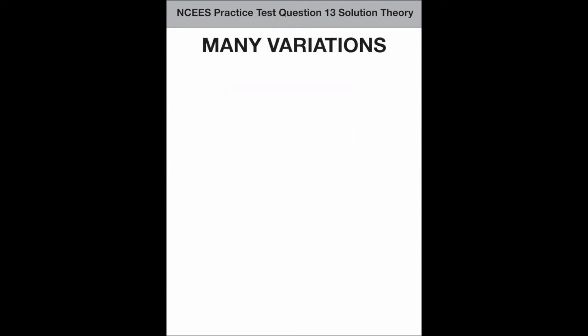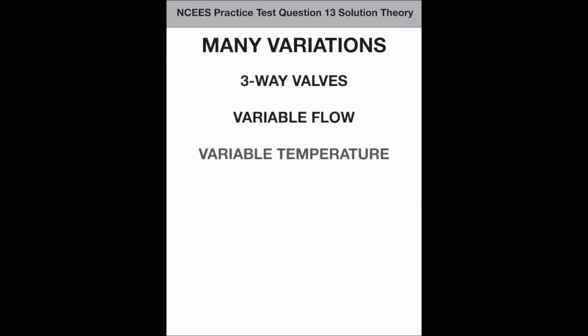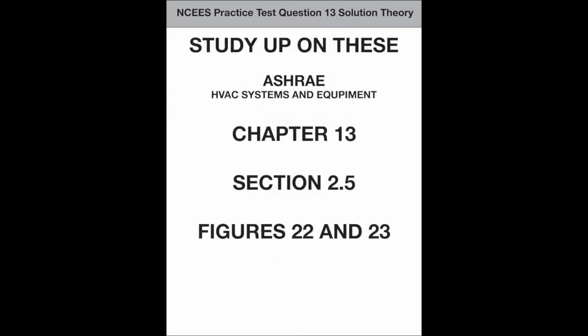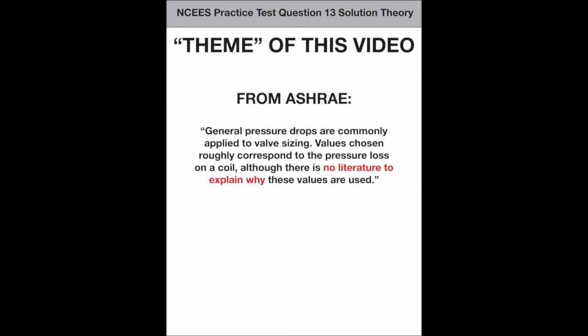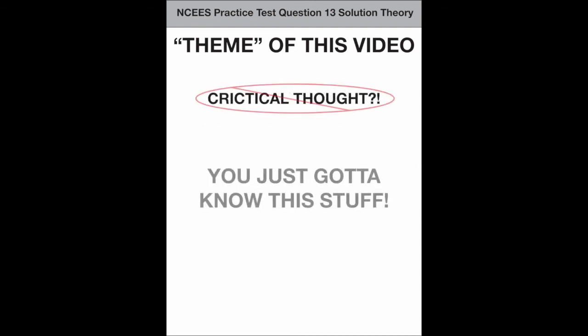Suffice it to say, there are plenty of variables, which include three-way valves: variable flow, variable temperature, mixing, diverting, etc. Study up on this. Again, go to ASHRAE HVAC Systems and Equipment Chapter 13, which is the definitive explanation on these sorts of things, and read Section 2.5, especially around Figures 22 and 23. It is in this section of the ASHRAE you will read two sentences which encapsulate the whole theme of this video. To quote, "General pressure drops are commonly applied to valve sizing. Values chosen roughly correspond to the pressure loss on a coil, although there is no literature to explain why these values are used." How's that for critical thought? To state it again, you just gotta know this stuff.